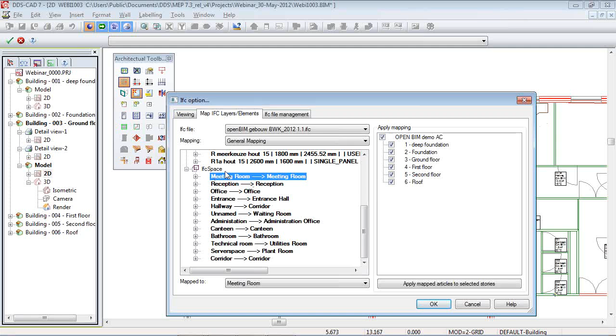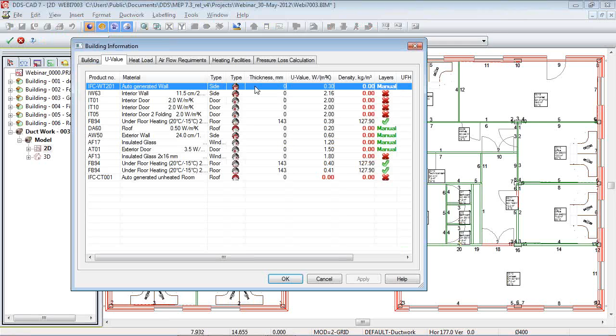Now I'd like to start with the technical discipline, first ductwork. I'll open the ground floor and do dimensioning, starting with a calculation of air requirements. Then I'll move to the duct system and calculate it, including automatic dimensioning. You can see the ductwork model has a different toolbar, but from the building model we still have the same information, now added with airflow requirements.